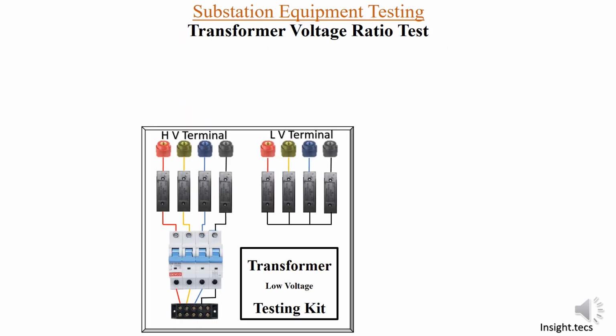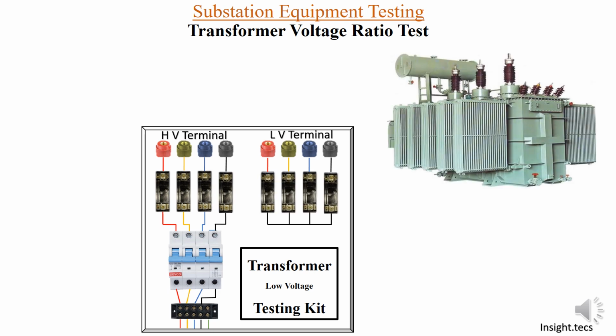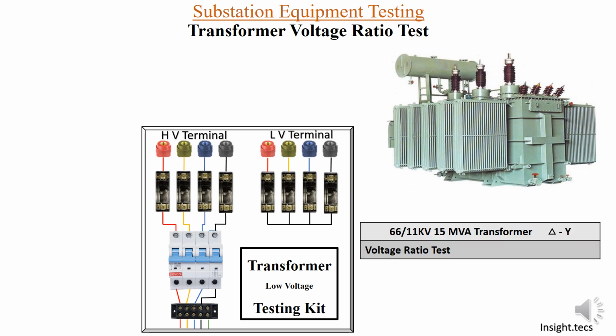So now, friends, let us begin with the voltage ratio test. First of all we will remove all the fuses, and this is the transformer on which we are going to perform the low voltage ratio test. The transformer is a 66 by 11 kV, 15 MVA transformer, and it is of delta star connection. So we are going to see the voltage ratio test for this transformer.